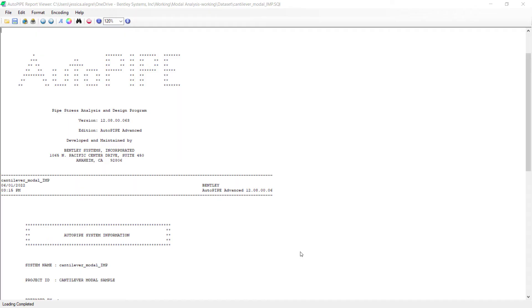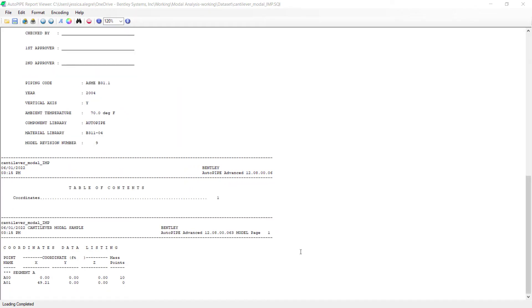In the coordinate sub report, if I scroll down to the bottom, I can see that there were 10 mass points added along the pipe between points A0 and A1. Remember, previously we added two points. Now we're adding 10 points. So we're taking this 49.21 foot section of pipe and dividing it into 11 equal pieces, refining the model much more than we did in exercise two.